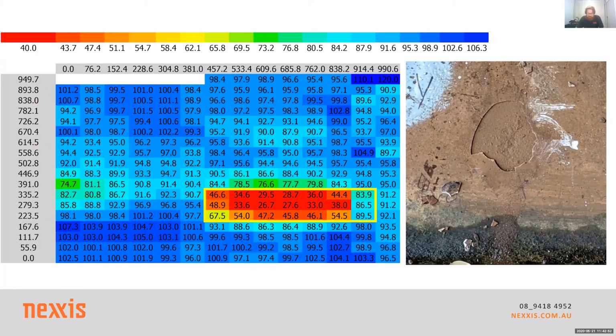The way the technique also works is that if you have extra supports or other backing material that's ferrous, that will start to show up. We can see here there were some supports that ran along, and the system picked those up quite well, which is why we're getting areas of elevated wall thickness. It wasn't an actual change in the steel plate, there's just stuff behind it.